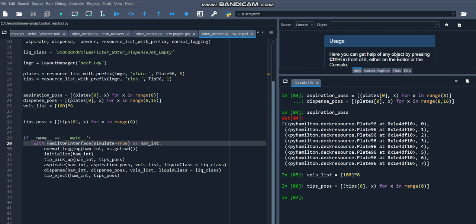Now that we've defined all the variables we need, it's time to look at the actual code that will be sending commands to the robot. This will be done in a context manager that declares the Hamilton interface, and we'll be running the interface in simulation mode. The first command passed to the interface will be the normal logging command, and this will set up a text file that receives all of the logged output from Venus.